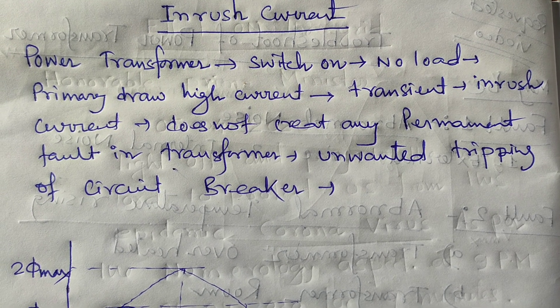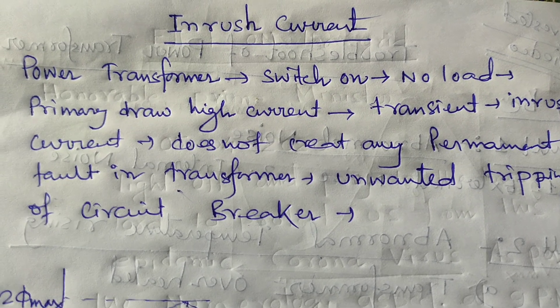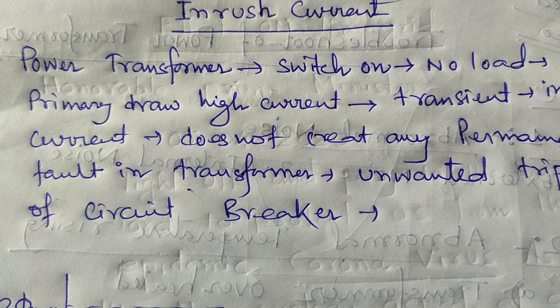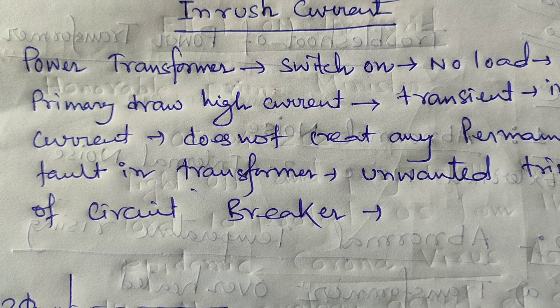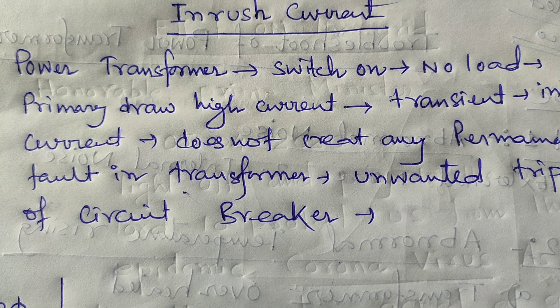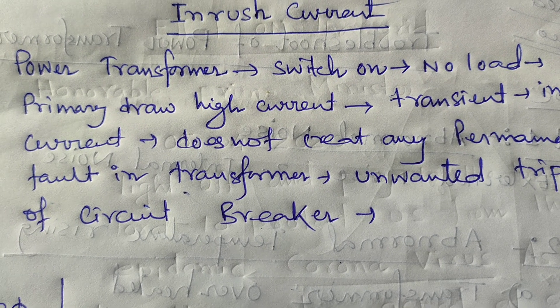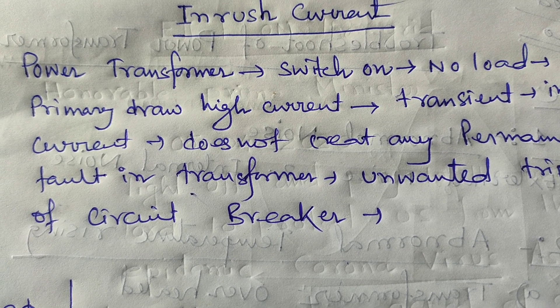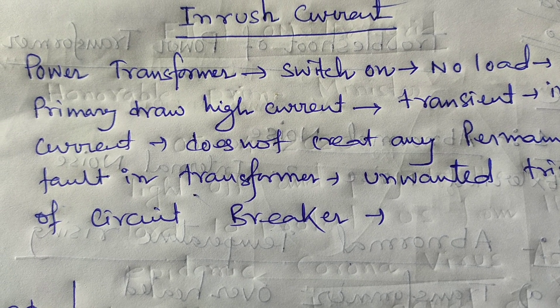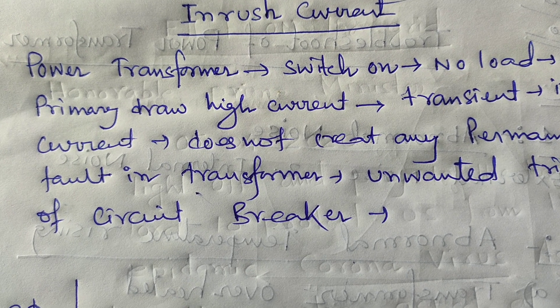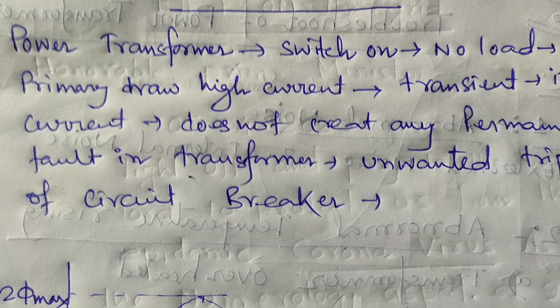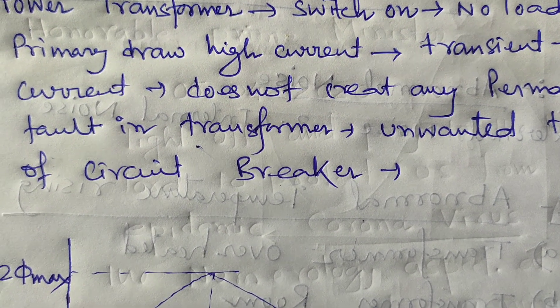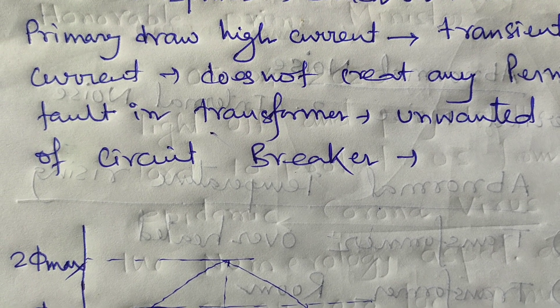Today our discussing topic is inrush current. Inrush current is the instantaneous high input current drawn by a power supply or electrical equipment at turn-on. During switch-on, this inrush current flows. It arises due to the high initial currents required to charge the capacitors and inductors or transformers. The inrush current is also known as the switch-on charge or input charge current. During turn-on, the discharged capacitors in the power supply offer low impedance, allowing high current to flow into the circuit as they charge from zero to the maximum value.